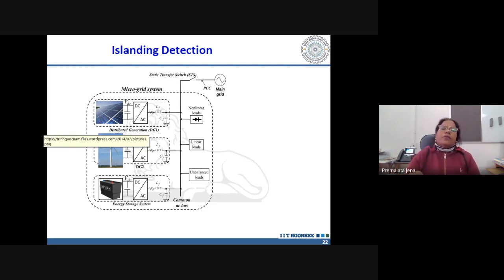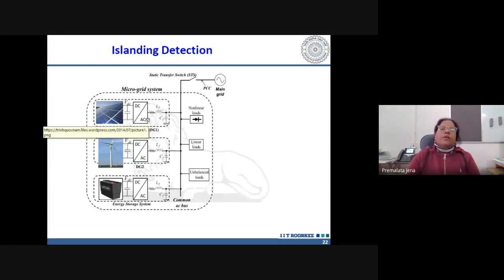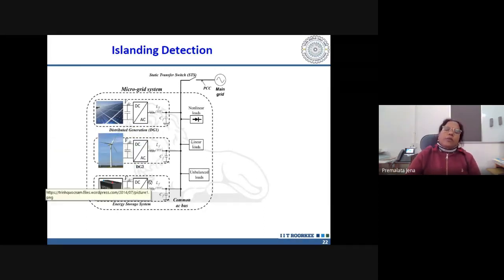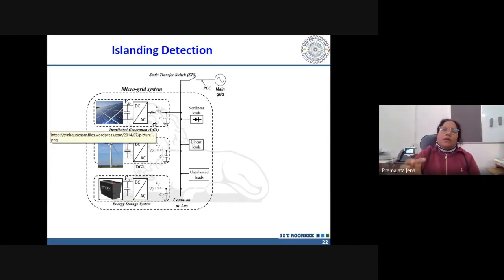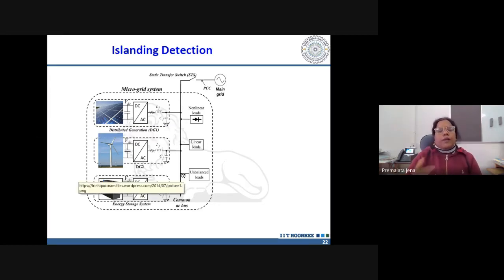Nowadays industry people like ABB are doing fantastic work, embedding this islanding detection technology inside the inverter of the solar system, wind system, battery, or whatever inverter-interfaced renewable sources are there, so that the inverter itself can detect that there is an islanding problem, meaning the microgrid is disconnected from the main grid, and de-energize the electronic devices. The renewable sources will stop supplying to the microgrid or loads, so that we can save our loads and avoid power quality issues.